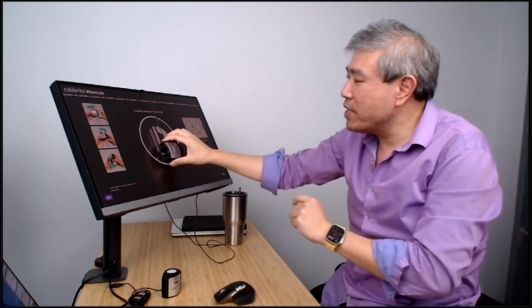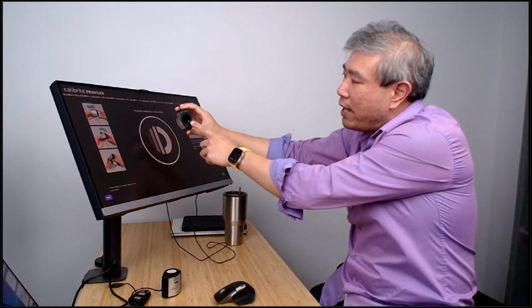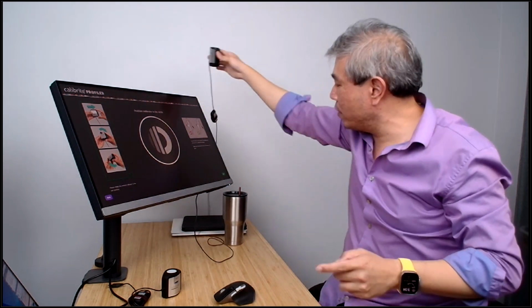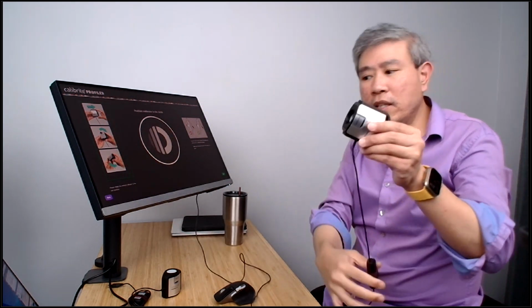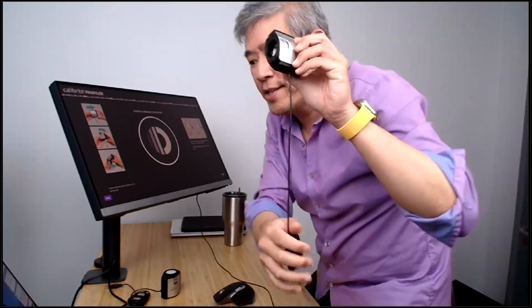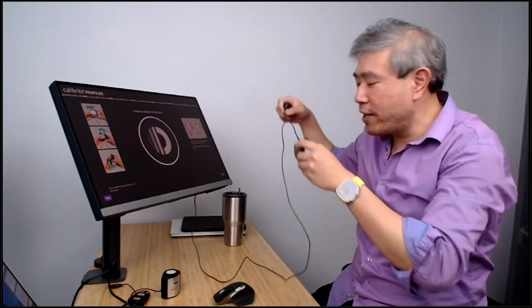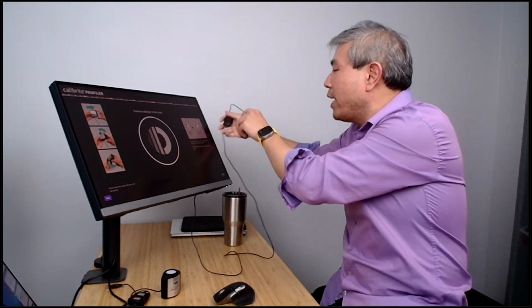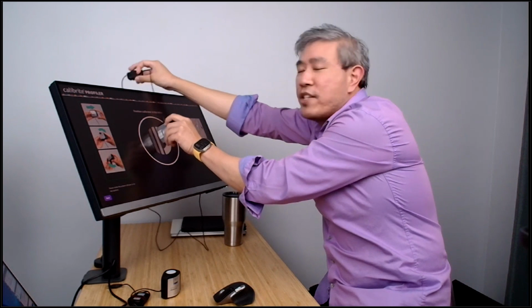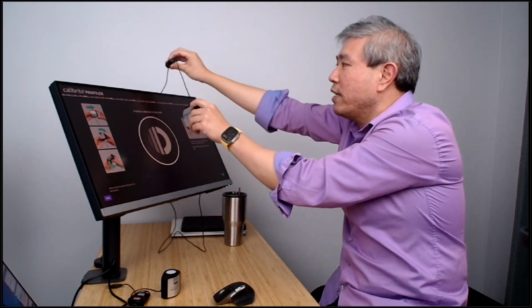Now, another thing I will also mention is that we can calibrate in the bright room like this, and that's perfectly fine. The reason why is because if we take a close look at the device right now, and I'll pull this to the side so we can see a little bit closer, you can see that on the front right there, there's not a lot of reflection material at the moment. These are felt lining, or some may call Alcantara material, but they're just really felt lining. And what they do is they prevent stray light from coming in when you're running the calibration.